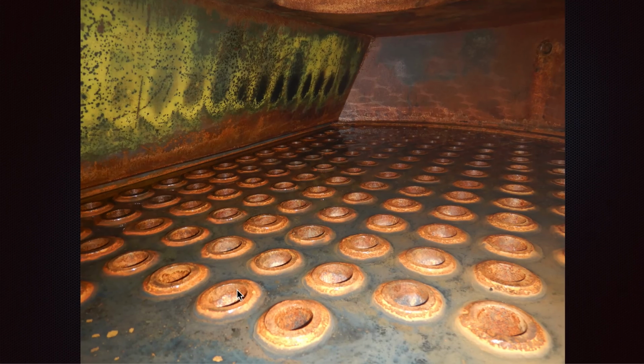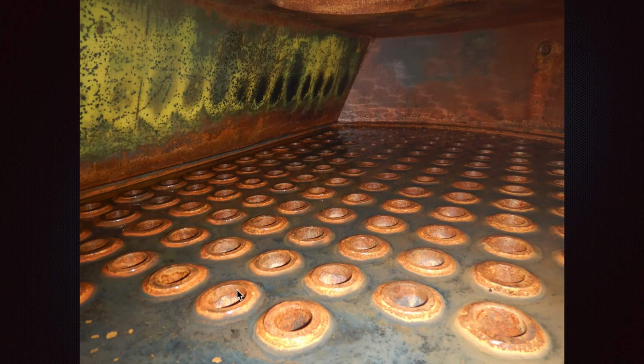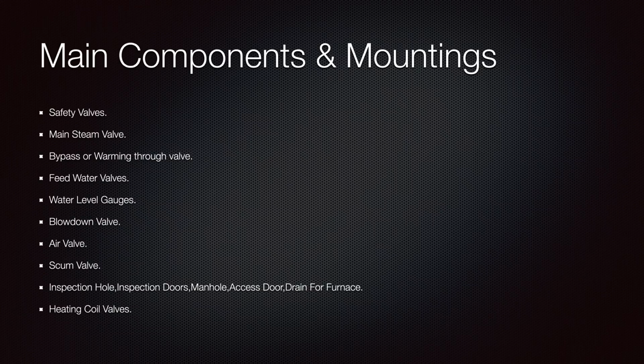The biggest problem that we can face with our boilers that work with exhaust gases is the tube size being reduced through the accumulation of carbon and any material which will be here. But as you can see here, everything is washed, and a good washed boiler is a boiler where we have a lot of rust here. This is a good indication.